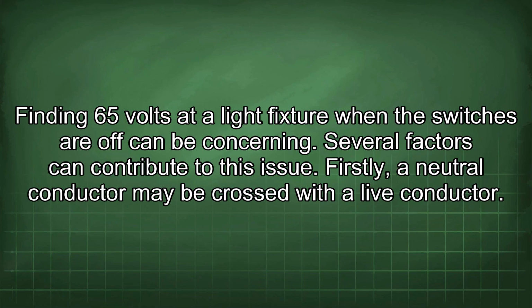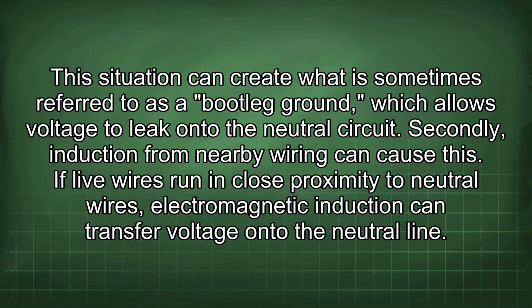Finding 65 volts at a light fixture when the switches are off can be concerning. Several factors can contribute to this issue. Firstly, a neutral conductor may be crossed with a live conductor. This situation can create what is sometimes referred to as the bootleg ground, which allows voltage to leak onto the neutral circuit. Secondly, induction from nearby wiring can cause this. If live wires run in close proximity to neutral wires, electromagnetic induction can transfer voltage onto the neutral line.